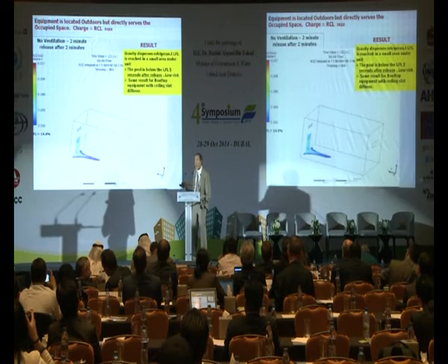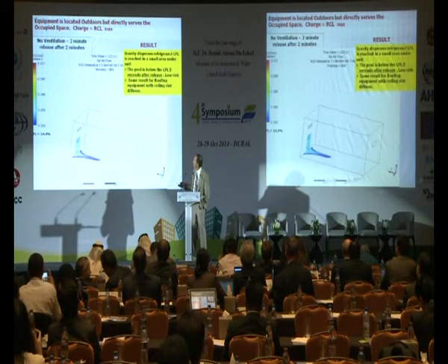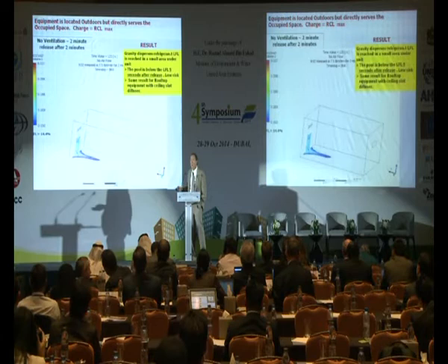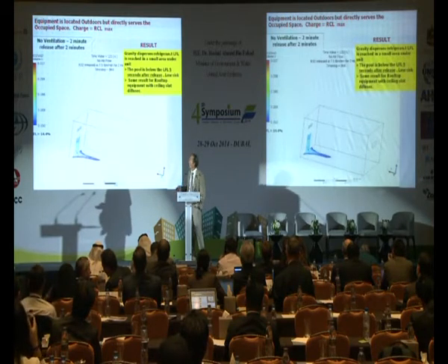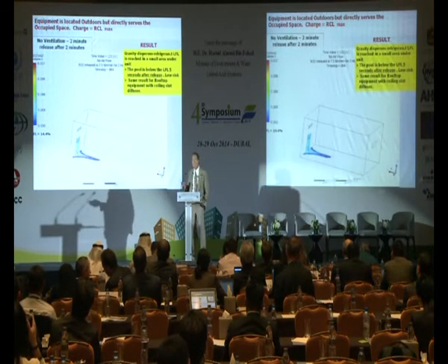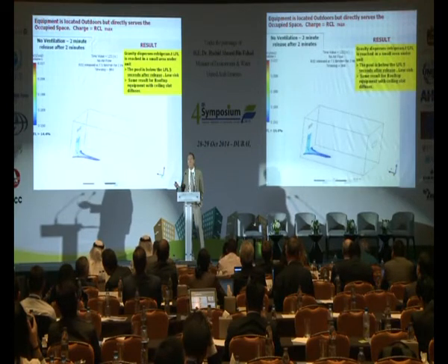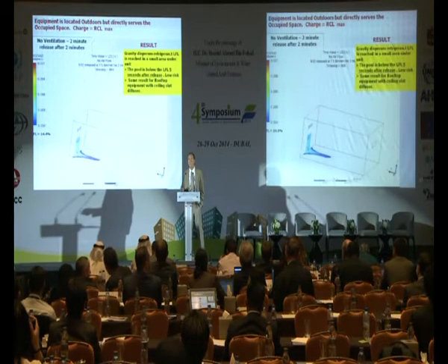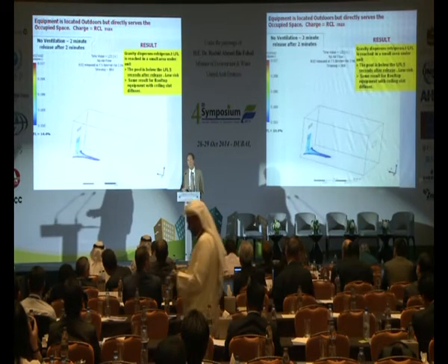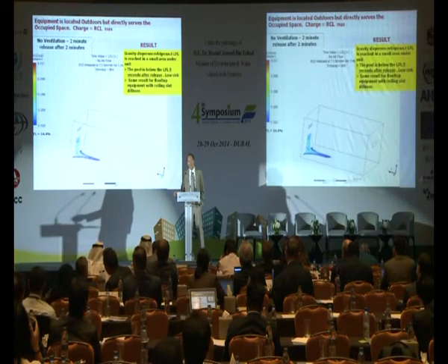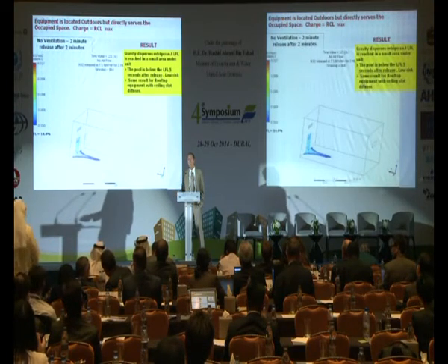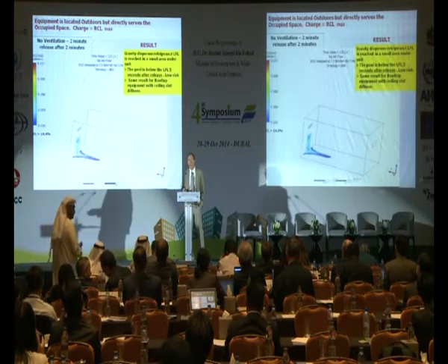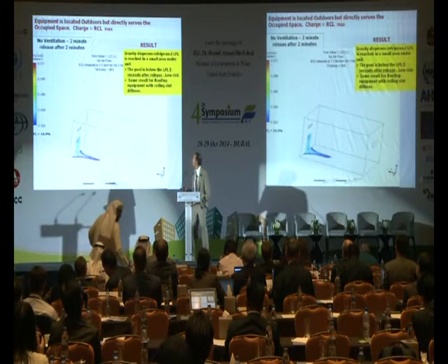The refrigerant through gravity alone is falling down the wall, and you get a very, very small zone that represents the LFL. But more importantly, once again, it only takes minutes, and that refrigerant pool has dissipated and falls below the LFL. Put exhaust air into that room, and it's gone even quicker. So the time, once again, is very, very short. So again, by design, if you put exhaust air in a room and you put a cassette up on a wall, you get an inherently safe design.